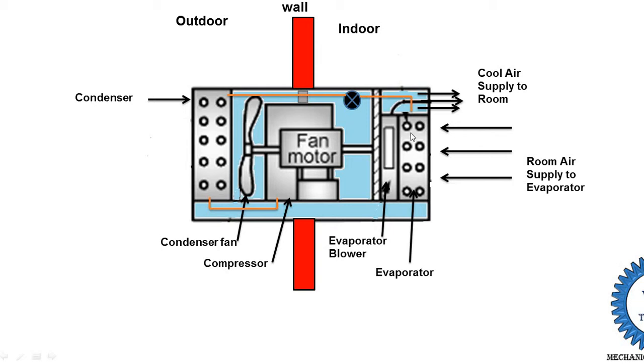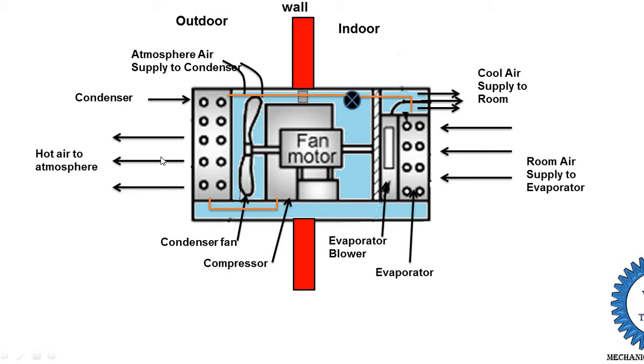After absorbing heat, the high-temperature refrigerant is supplied back to the compressor and then passed into the condenser, where the heat is rejected. A fan is provided to supply atmospheric air toward the condenser. That air transfers the heat, and the hot air coming out from the condenser is released to the atmosphere. This is the complete working of the window air conditioning system, which is the same as a refrigeration system with one fan and a blower added.